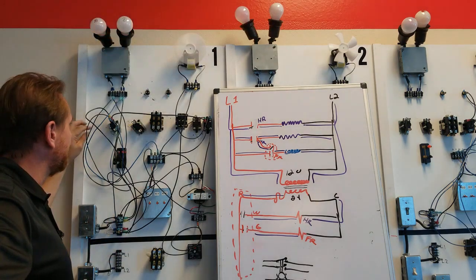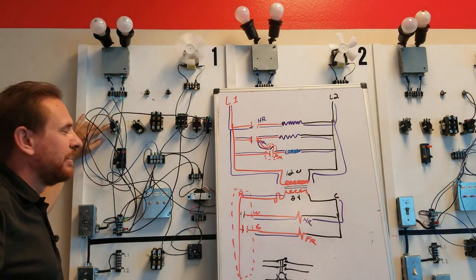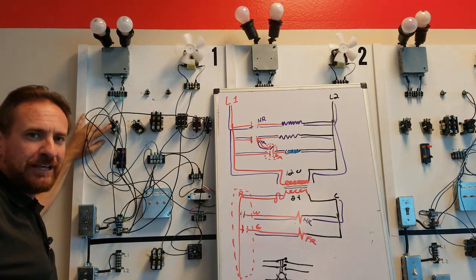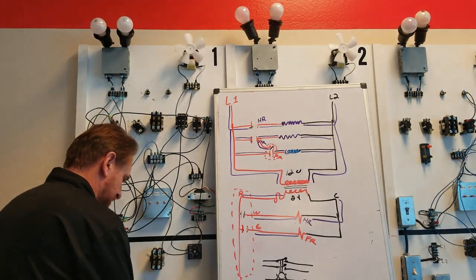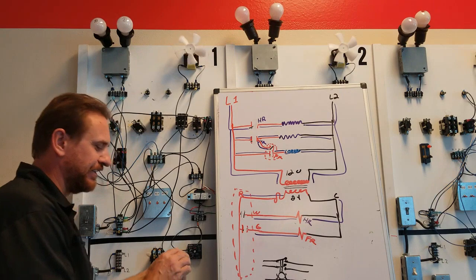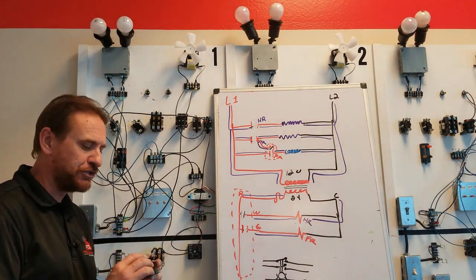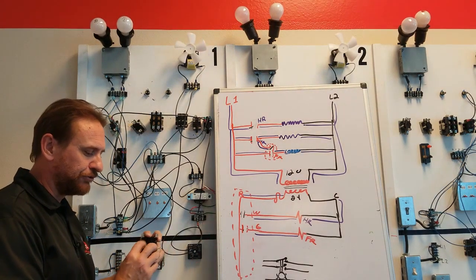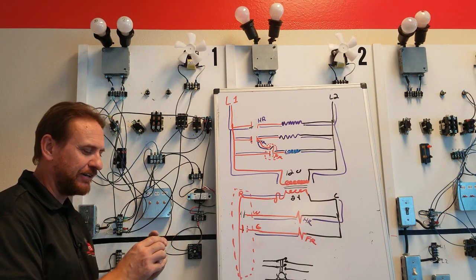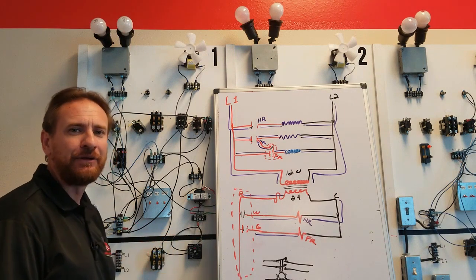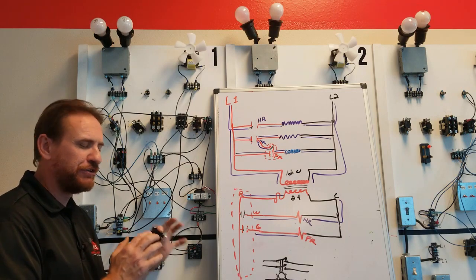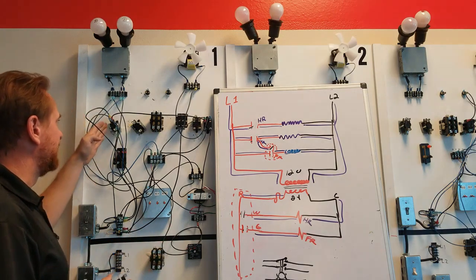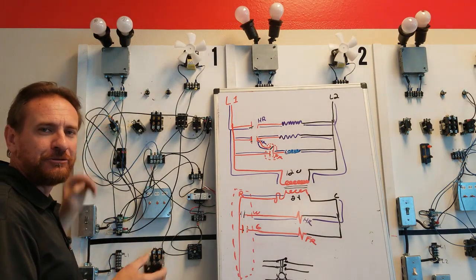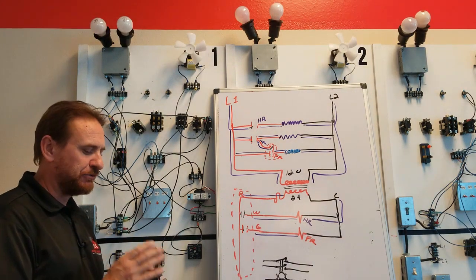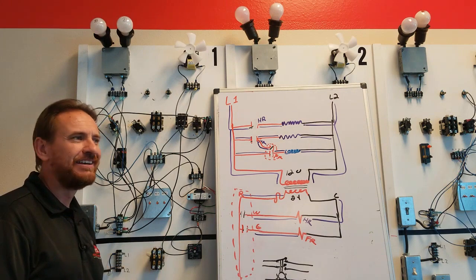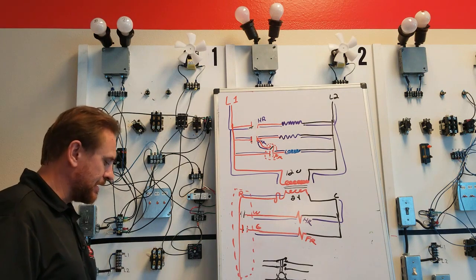You can buy these in tons of different sequencers and times, time on, time off. When you replace them, just because you go to the supply house and you see this and it looks the same doesn't mean they're the same. You want to make sure you check these numbers. Google these numbers, ask for a map of how they work or how they number them, but you want to make sure that you get the same one. This one had a pretty quick on delay, but it took a little bit longer for that off delay to happen. So we want to make sure that we set that up so we don't change that sequence.